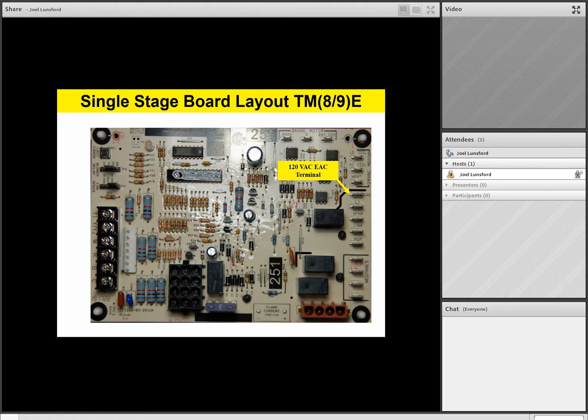That L1 is a 120 volt input to the board to power up the line voltage or the 120 volt devices, for instance, like the transformer and the motor itself. Remember, we commented that the motor itself is going to have power to it all the time, and so the power coming into the board to power up the 120 volt components will come in on the L1. The XFMR is 120 volt output to the transformer to power the transformer up. Where it says line, that's a 120 volt line to power up the motor. So again, the ECM motor is powered up all the time, and that 120 volt from the line terminal will be that hot wire, if you will, that 120 volt line voltage power going to the motor all the time.